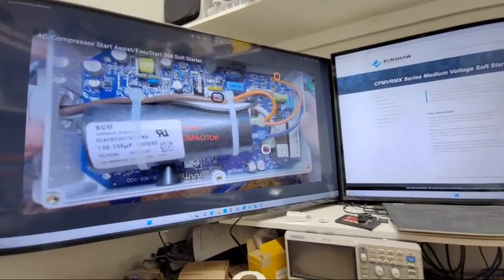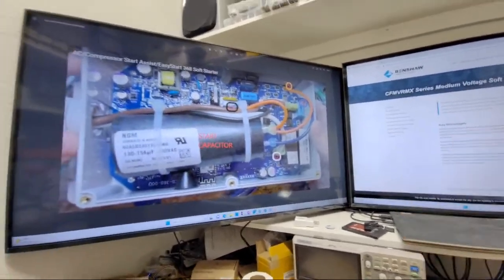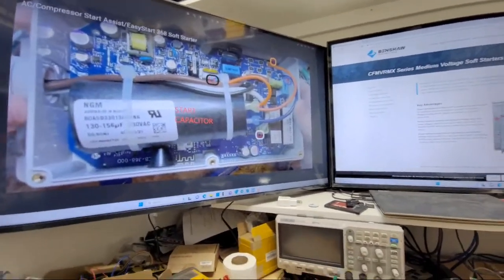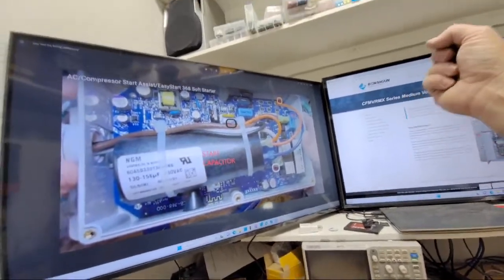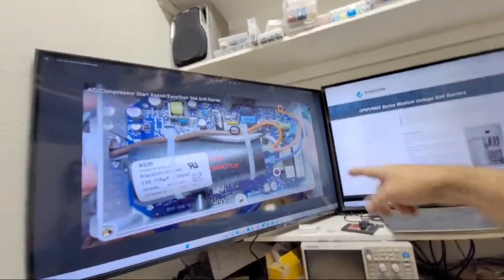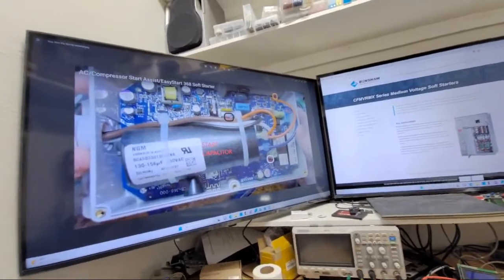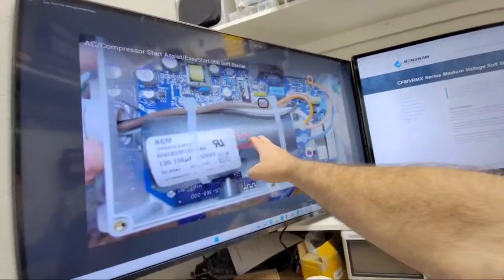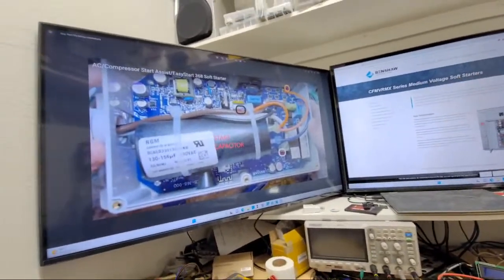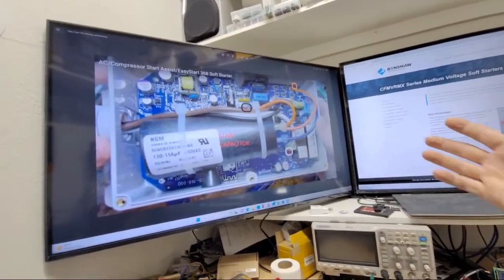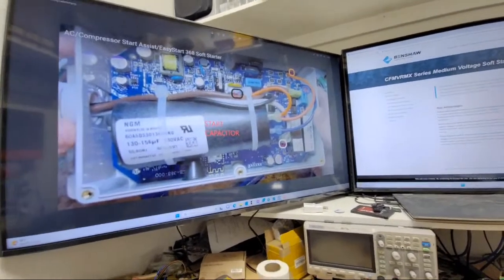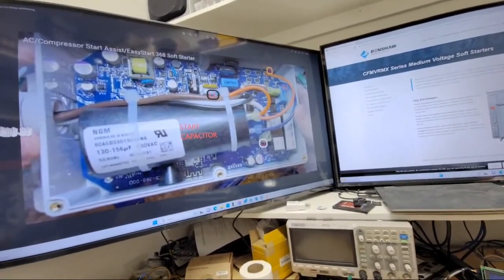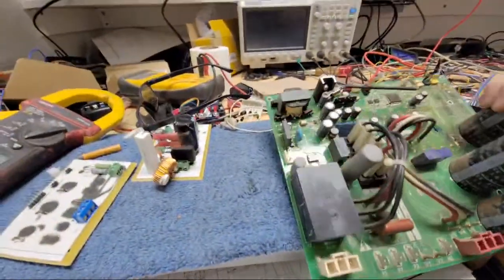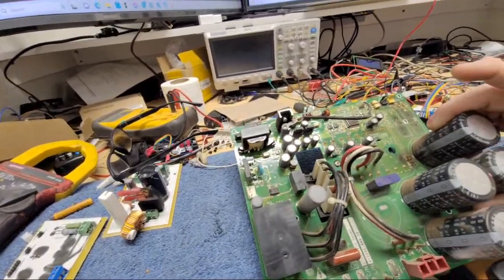I'm thinking it's just adding a delay so that your other motor that wasn't going through this is already up and running, and 5 seconds later your compressor is going to start. It might do some tweaking with those, but it's probably just throwing those relays and electronically paralleling in your start capacitor. I think they're doing something to adjust that, but I don't even see any current sensors in this thing - like this thing's gonna have current sensors. Maybe it's not on this board.